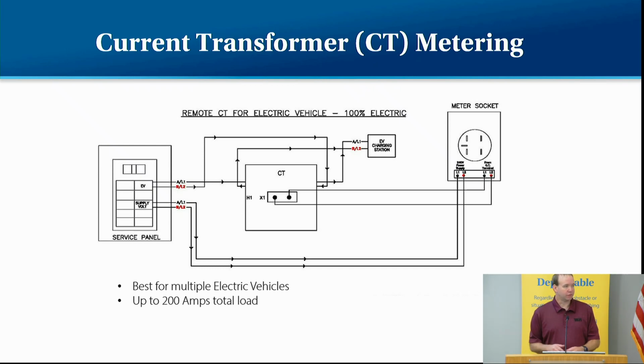Just curious, because obviously we're talking an EV breaker, nobody's going to want to run 6s or 4s, depending on what kind of cable, just to power up your board. Yep. A lot of people just put a 15 amp circuit. There is fusing in there, so there is a little bit of leeway on circuit size, but you have to verify your length of wire and everything on that. So the CT installation is fairly simple.